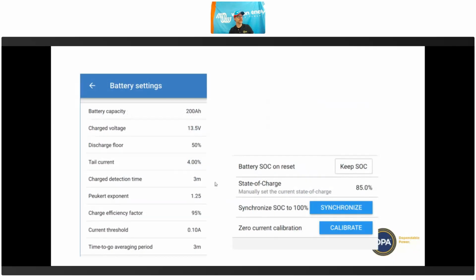Now in the settings here, this is a really important bit to make sure that the battery monitor is going to operate properly. So the most important thing is the battery capacity. If you've got a 200 amp hour battery, you need to tell it it's a 200 amp hour battery, because then it knows that if it sees 200 amp hours having gone through the shunt, it should be down at 0%. If you put 400 amp hours in there, it's going to read 50%. So it's important to get this value correct.